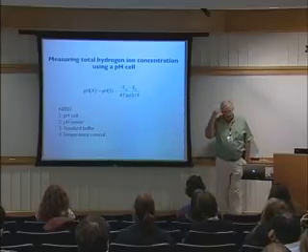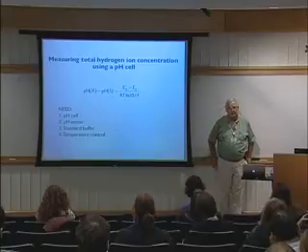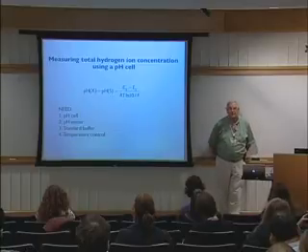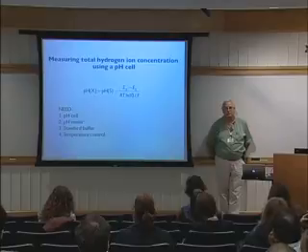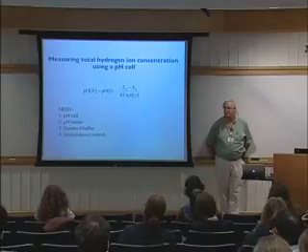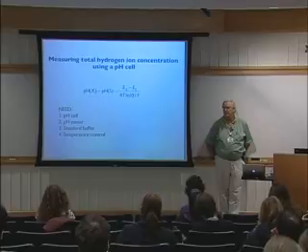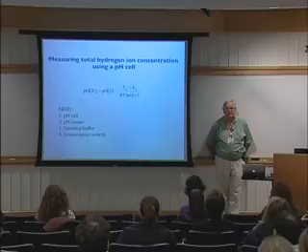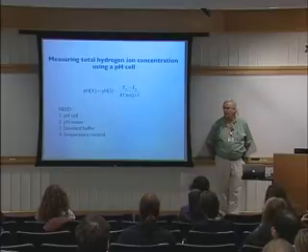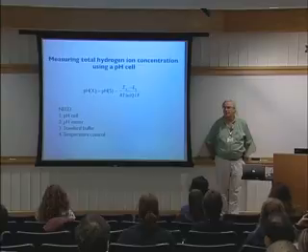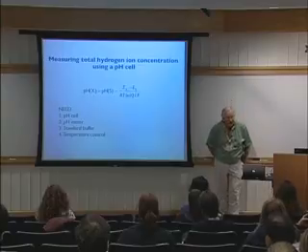And you could do a quick estimate for temperature control. It's not that demanding. 60 millivolts per pH unit. Temperature is about, for this kind of arithmetic, 300 degrees Kelvin, 300 Kelvin. So if you're within 1/10 of a degree, you're going to be okay. That would be my aim for pH measurements, that you had the temperature at that level.